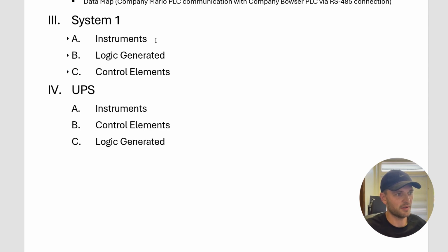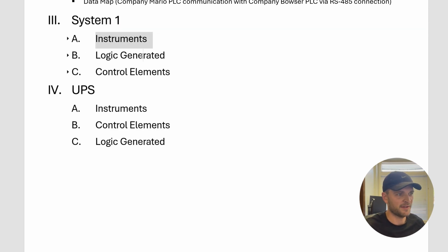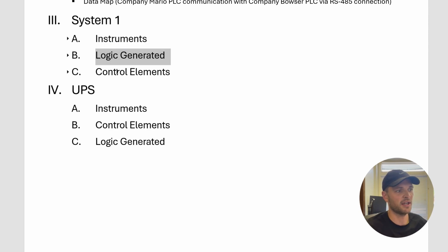So we have instruments. So these are your input devices. These will be pressure transmitters, temperature transmitters, right? There's no action. They're just reading data into the system. The second section is logic generated. I'll go over this more in depth, but essentially, you might have a pressure transmitter high alarm plus a valve status plus third party data that all needs to trigger an event or trigger action in a control element, right? So that goes here in logic generated. And then the control elements are output elements, right? So these are valves, pumps, anything that affects the hydraulics of the system.